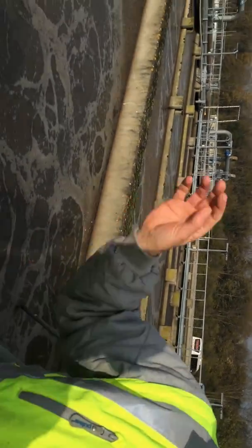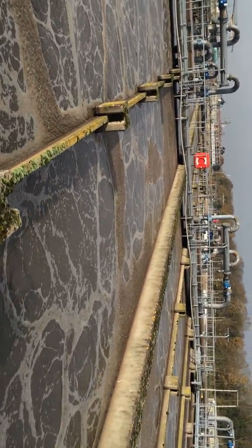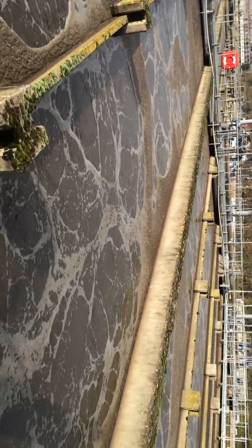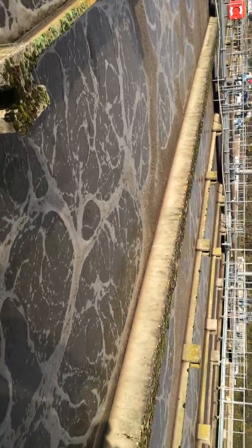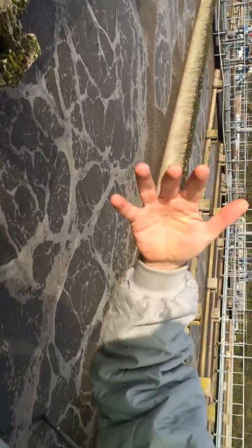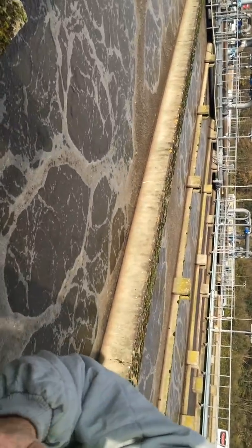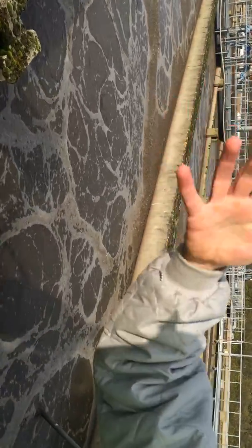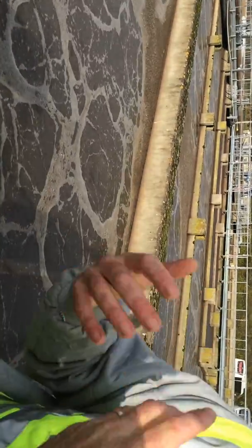So what we're doing is effectively the primary treatment process removes all the settleable material. In the secondary treatment process, a lot of what we're doing is converting what we can't settle into biomass, which we can settle. So again, we'll use a sedimentation stage to take the excess biomass out. But the important thing is we're feeding and growing bacteria all the time. So this process is producing excess biomass all the time, quite a high yield. So for every kilogram of BOD that comes into this system, we're probably producing about 0.8 or 0.9 kilograms of biomass with growing bacteria.